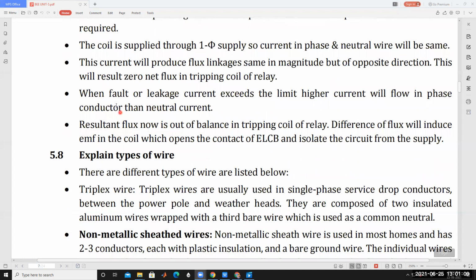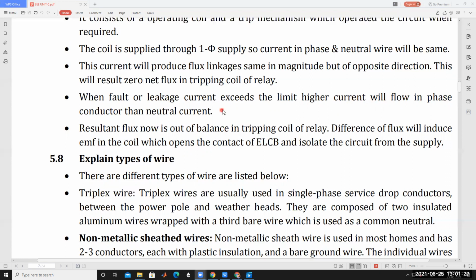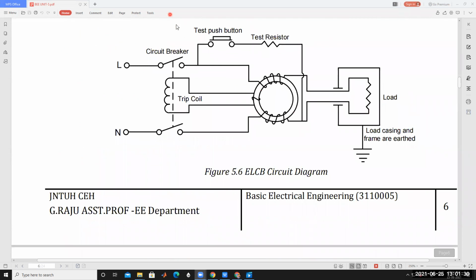Under fault conditions, what happens when the fault or leakage current exceeds the limit? Higher current will flow in the phase conductor than in the neutral. For example, if a ground fault takes place here, this is called an earth leak. This is the load. So if a fault occurs like this, what happens?